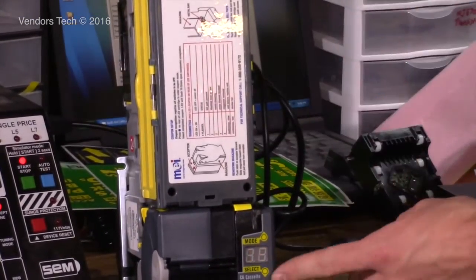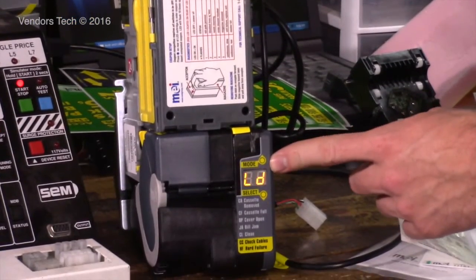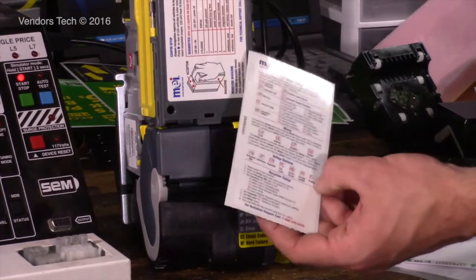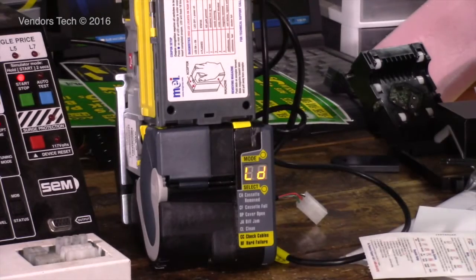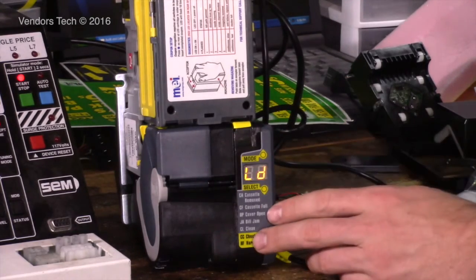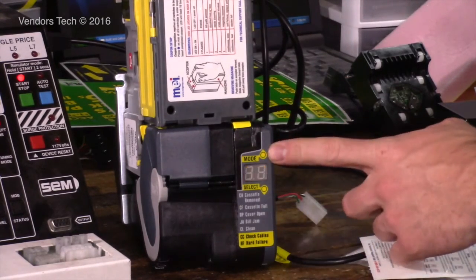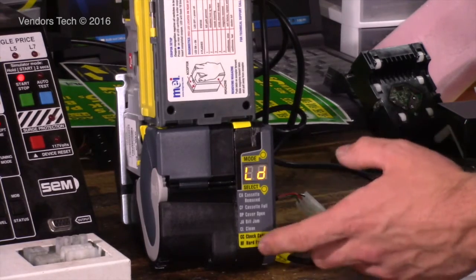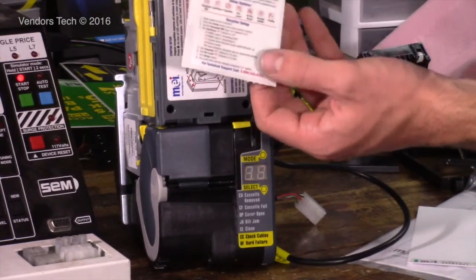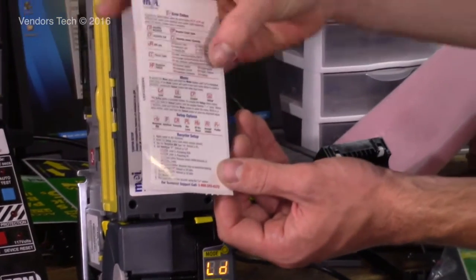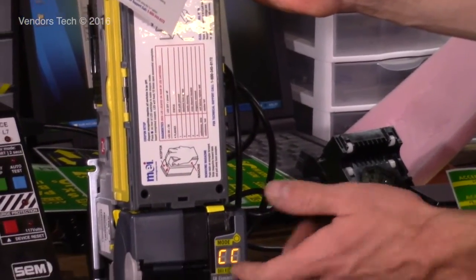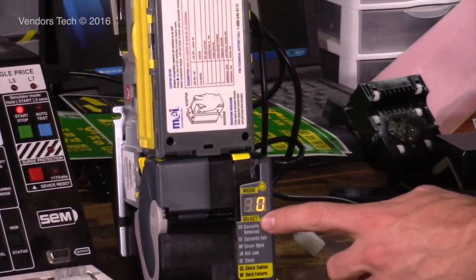The reason that we have to hold the select button and get those 2 lines to flash is because the setup mode is a hidden part of the programming. If we just held the mode button down and went into programming, you'd only get 3 options in the menu: load, unload, and coupon. We have to hold the select button down and get those 2 lines to flash in order to get into the setup mode.